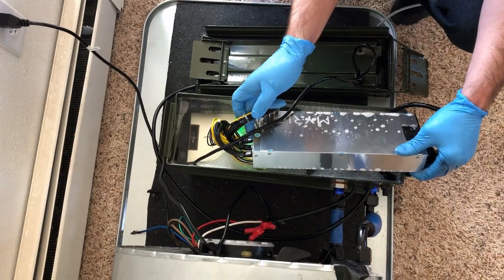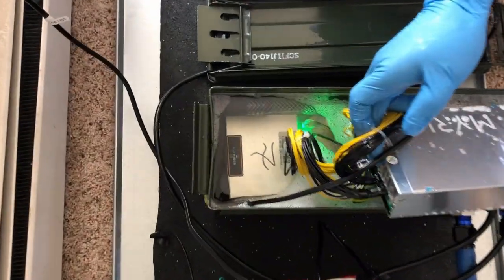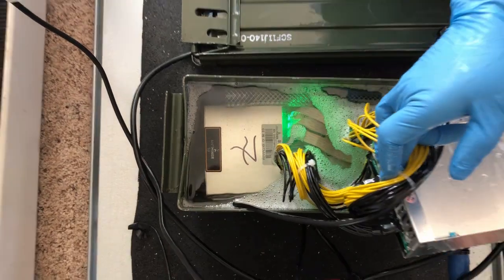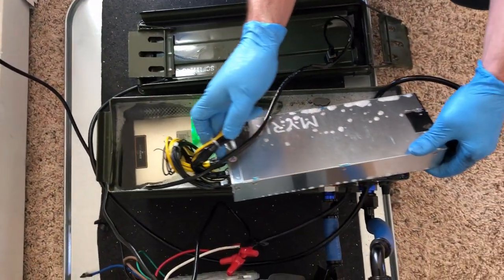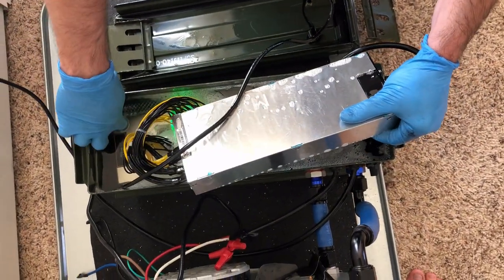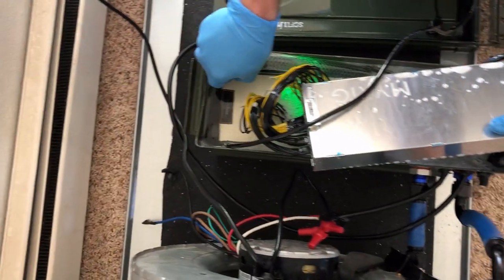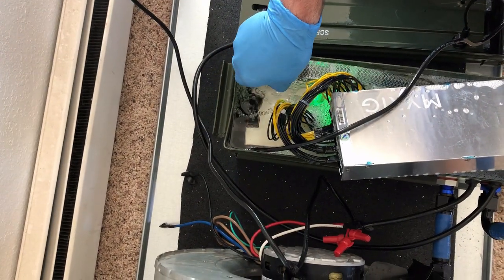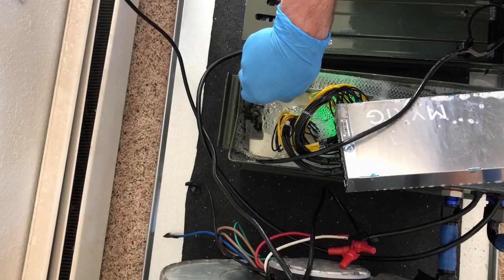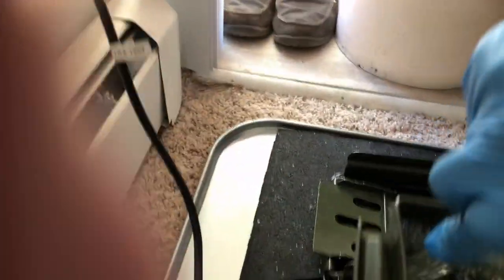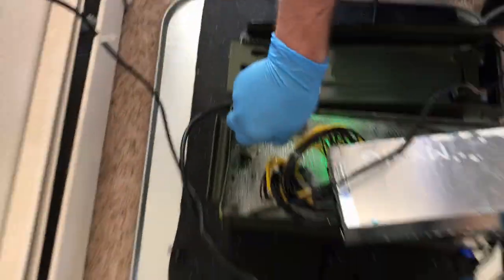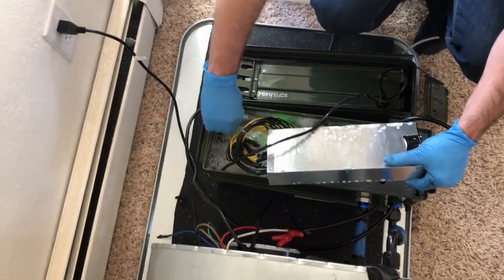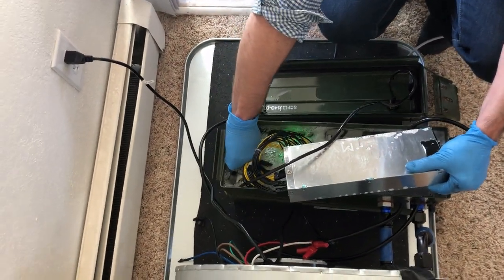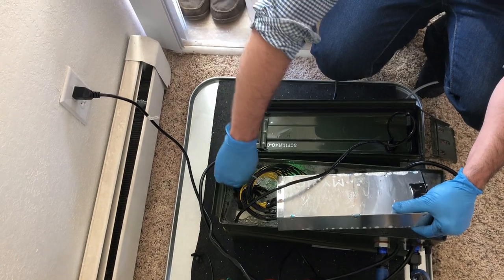So if we pull out our power supply from the oil, you can see all the lights are on and the machine is running just fine. We do have the oil return, try to do this without spilling. You can see there's a fair amount of oil being pumped through. If you have less than this, check for kinks. You need a lot of oil to go through your machine.